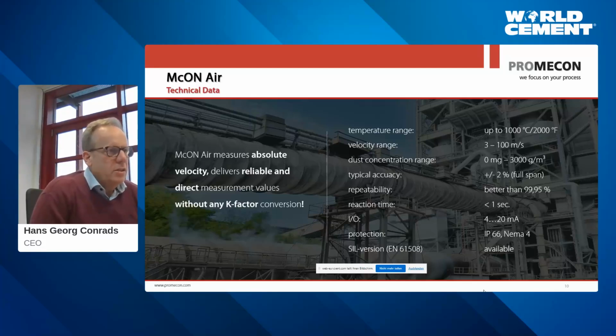The measurement range goes from above ambient. So whenever you have, let's say, starting from 50, 60 degrees, it goes up to 2000 degrees Celsius. In this version that I'm showing you here, the version with the antenna, we can go up to 1000 degrees Celsius. So up to tertiary air temperature levels. The velocity range is from 3 meters per second up to 100 meters per second, strictly linear. Strictly linear. We have a turn down ratio in this way over 20.